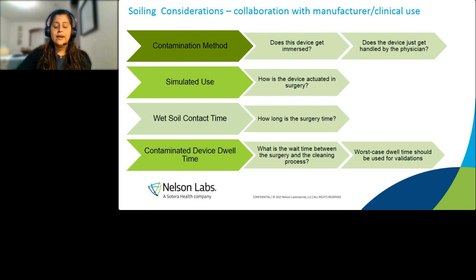Now, when we have selected the sites or the worst case devices for testing, we're working with the manufacturer to figure out how we are contaminating these. How are we flushing them? Are we soiling them with contaminated gloves? What are we doing? All of these things that I've outlined here is what we are discussing with the manufacturer to figure out how this device is used and how we can actually mimic the process that's happening in the healthcare facility, to make sure that the cleaning validation is done accurately to what is happening at the facility.